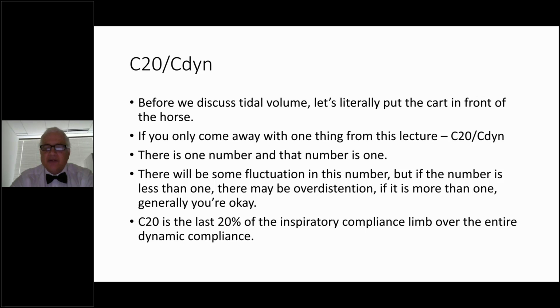There will be some fluctuation in this number, but if this number is less than 1, there may be overdistension, and you may be in a position where you're giving too much volume to that baby. If it's more than 1, generally you're okay. So what is C20/Cdyn? C20/Cdyn is the last 20% of the inspiratory compliance limb over the dynamic compliance. And I'm going to show you an example of that graphically, but I think now at this point we can talk about tidal volume.